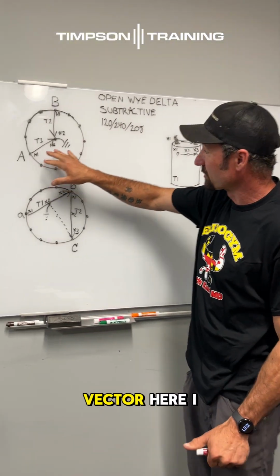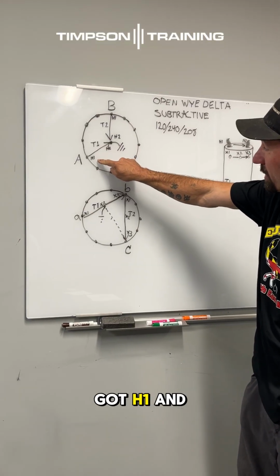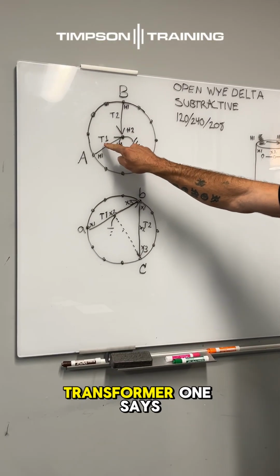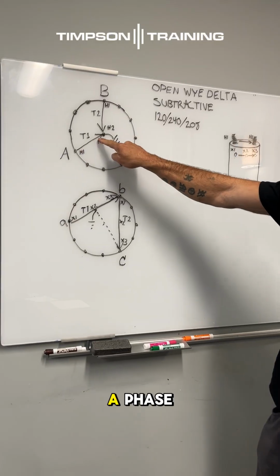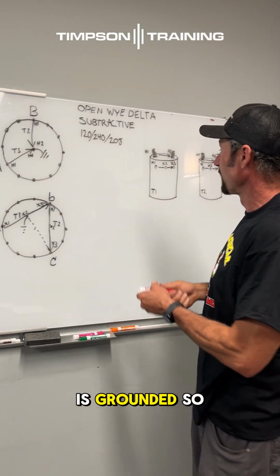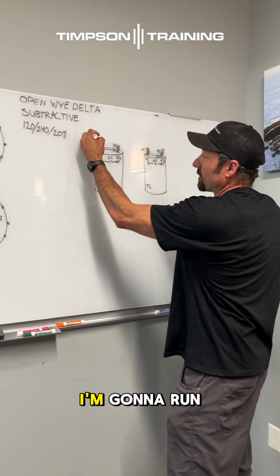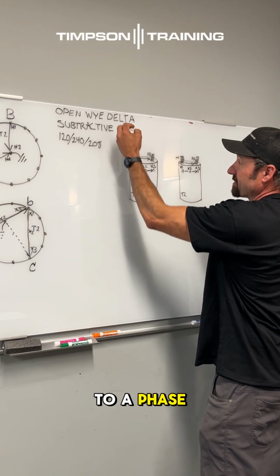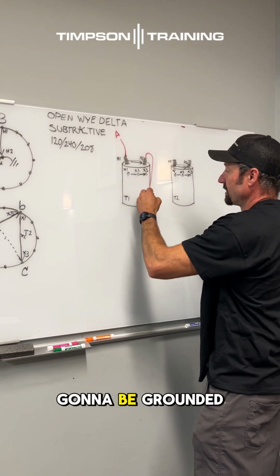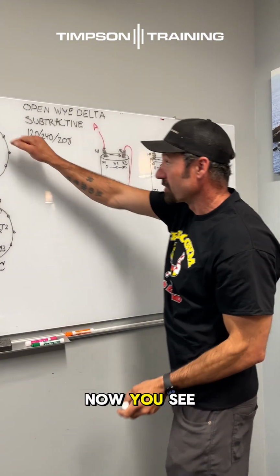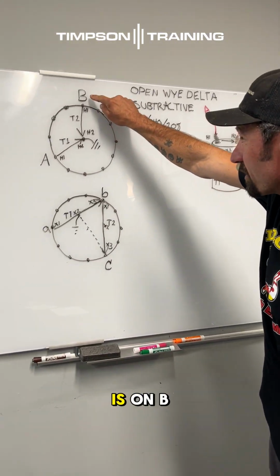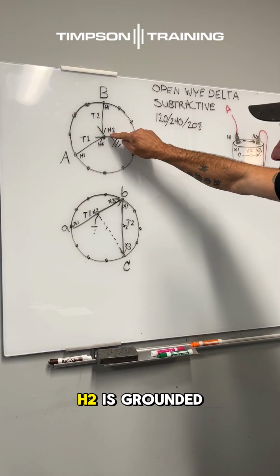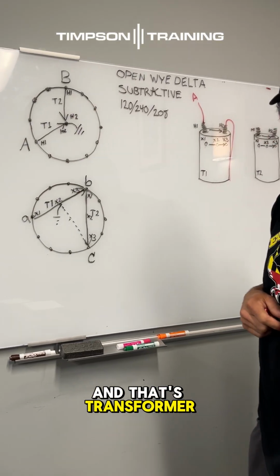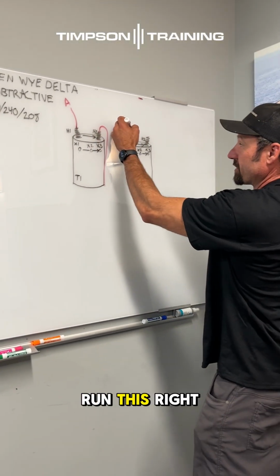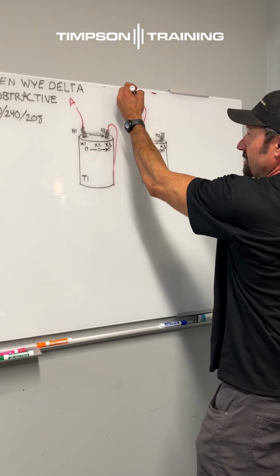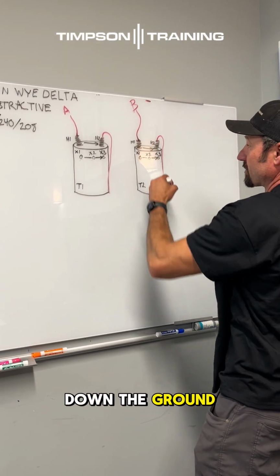So if we look at the vector here, I got H1 and H2, transformer 1 says A phase, and the H2 is grounded. So I know that right here, I'm going to run this H1 up to A phase, and this one's going to be grounded. Now you see B phase, H1 is on B phase, H2 is grounded, and that's transformer 2. So I'm going to run this right up B phase and run this down to ground.